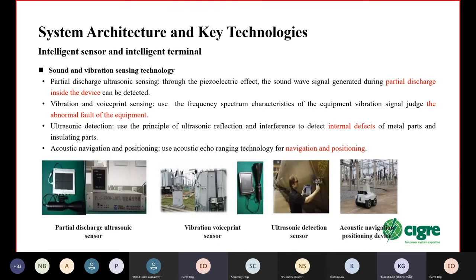And the second type used widely is sound and vibration sensing. Partial discharge ultrasonic sensing works through the piezoelectric effect. The sound wave signal generated during partial discharge inside the device can be detected. Vibration and voiceprint sensing uses the frequency spectrum characteristics of the equipment vibration signal to judge abnormal faults of the equipment, and ultrasonic detection uses the principle of ultrasonic reflection and interference to detect the internal defects of the metal parts and the insulating parts.